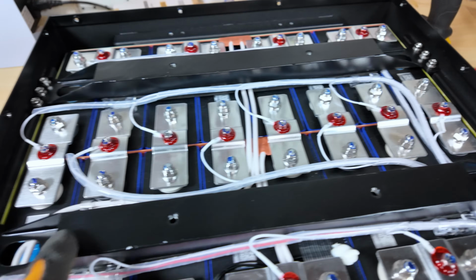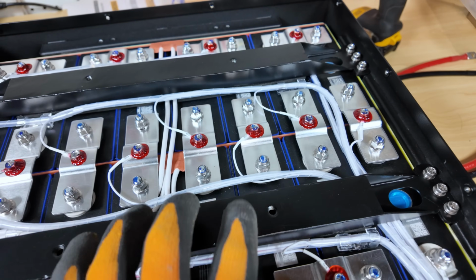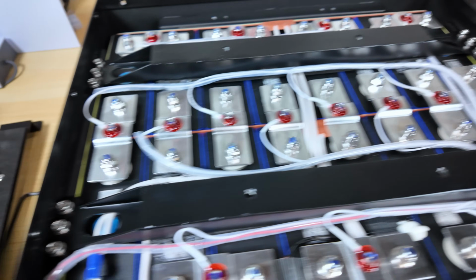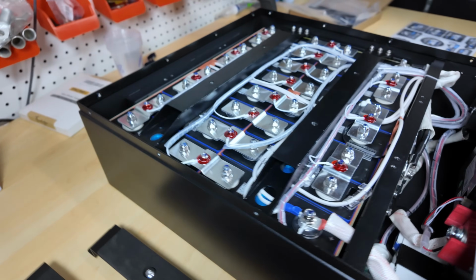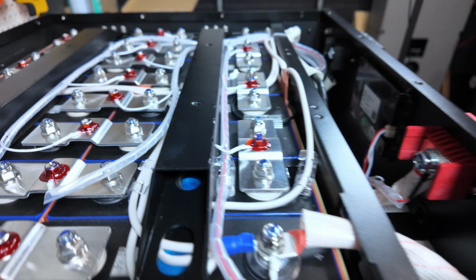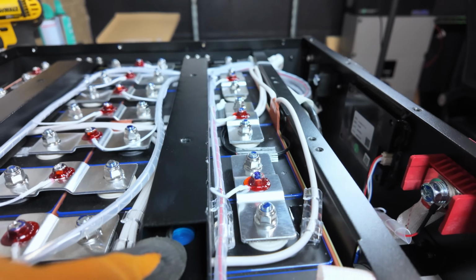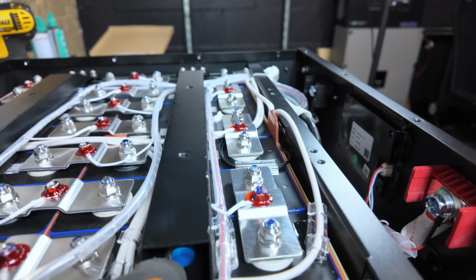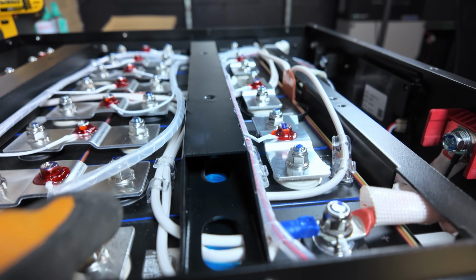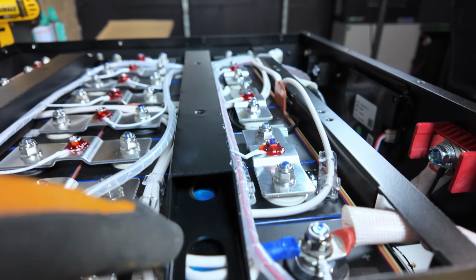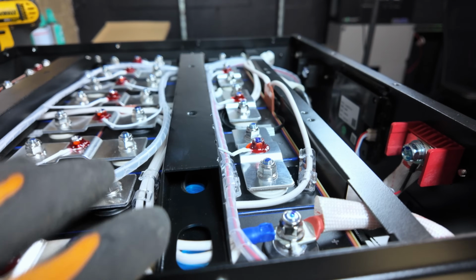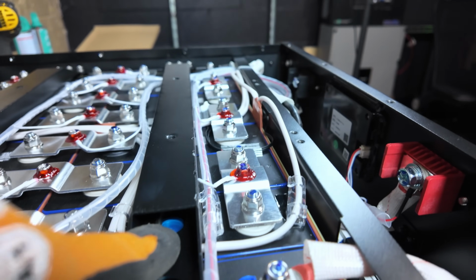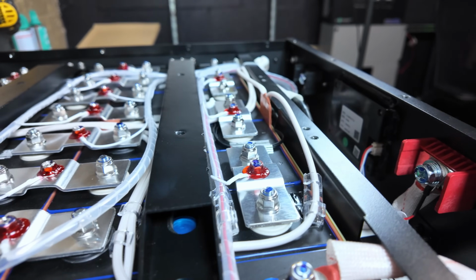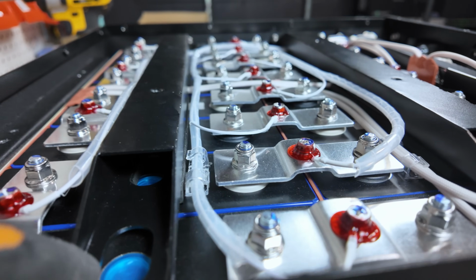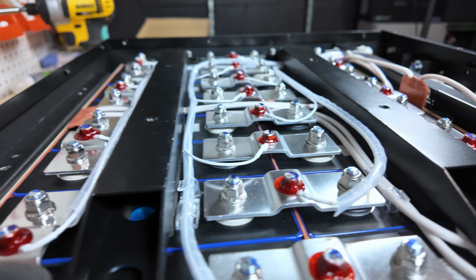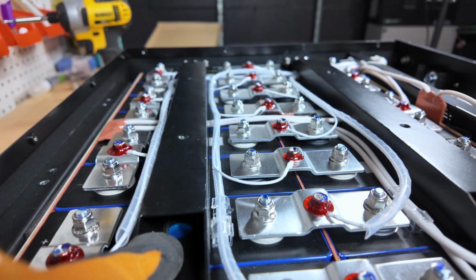Now, while they do have this bar sealed along the top for extra support over top of the cells, I don't know if we're going to be able to see this or not, but if I come over here and look inside, you can see they have vent holes exposed on the inside of this channel. So that way, if for whatever reason a cell had to vent, it doesn't have something blocking the top of the vent. And across here you can see they've got it on this one as well. That light blue is the vent on the cells.